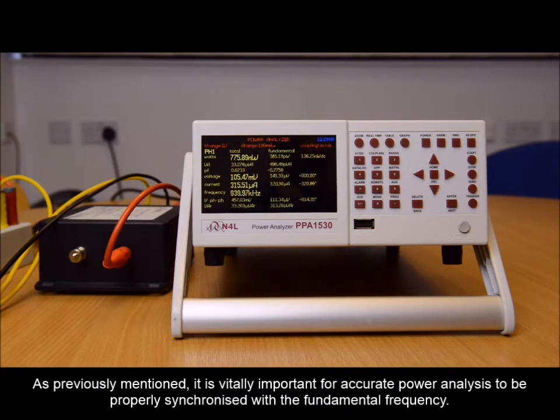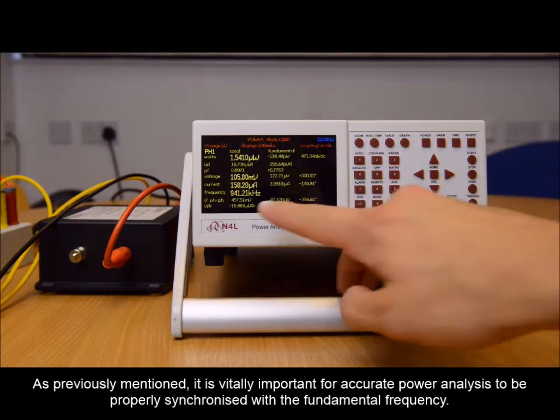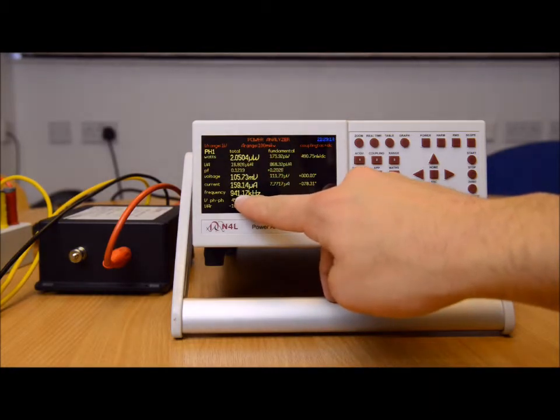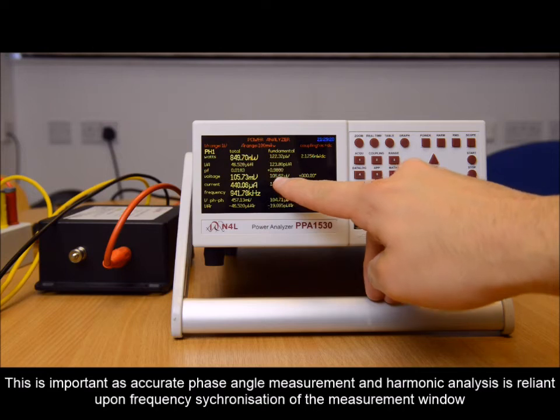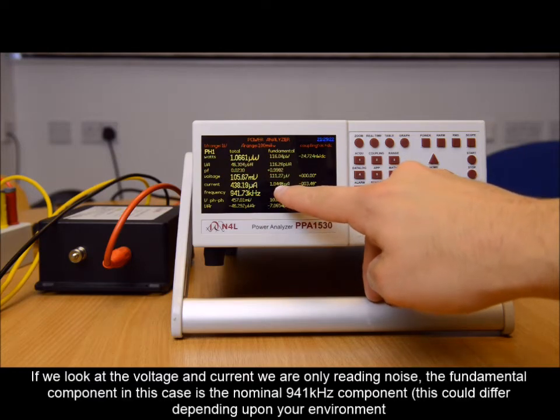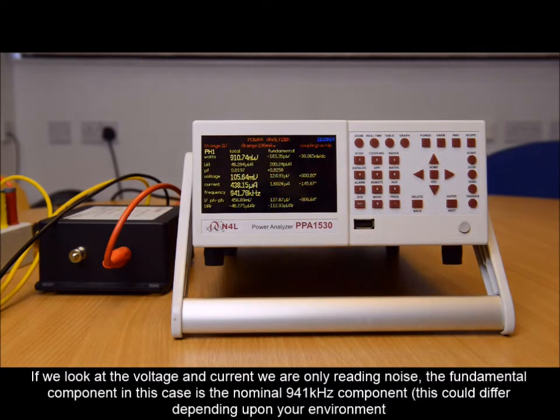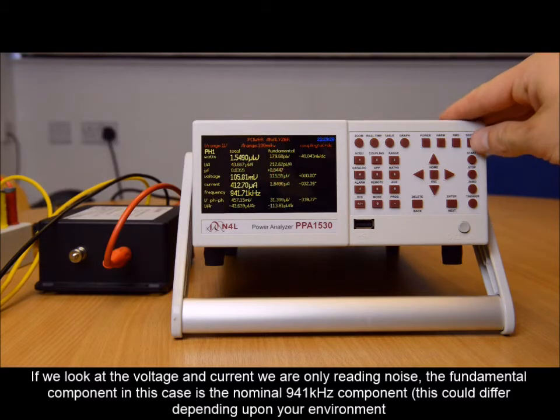As previously mentioned, it is vitally important for accurate power analysis to be properly synchronized with the fundamental frequency. This is important as accurate phase angle measurement and harmonic analysis is reliant upon frequency synchronization of the measurement window. If we look at the voltage and current, we are only reading noise. The fundamental component in this case is the nominal 941 kilohertz.